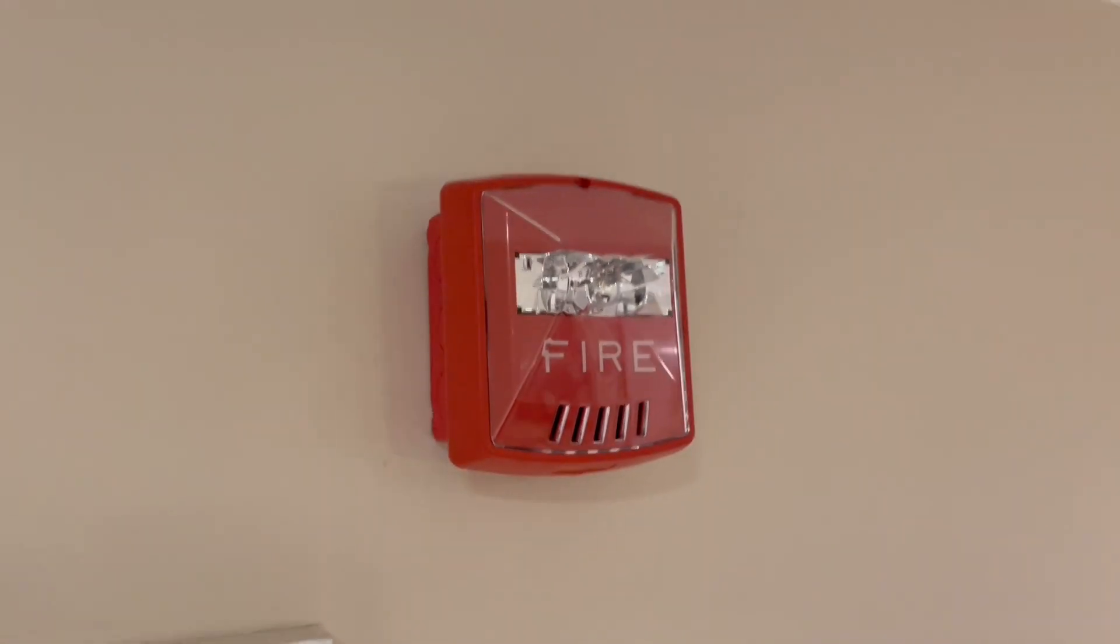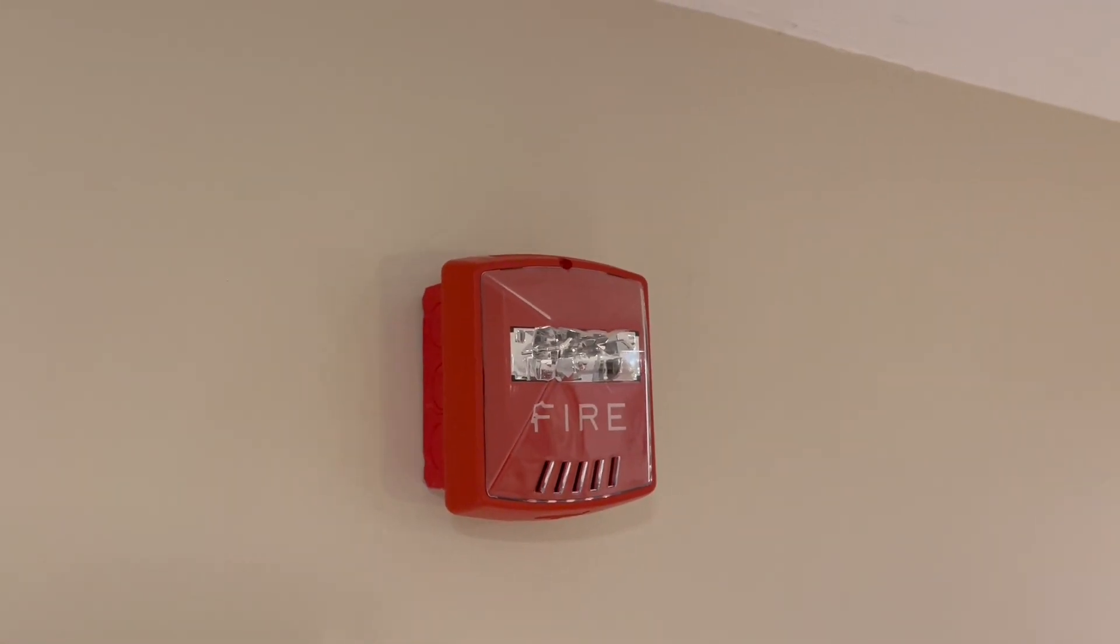Either way, now that this is installed nice and easy, what we're going to do is set our candela, which in this case I'm just going to do 15, and then also the volume selection. This is going to be code 3 low volume. So you just kind of hook it on the top there and then snap it on, and there you go. Really elegant looking device.